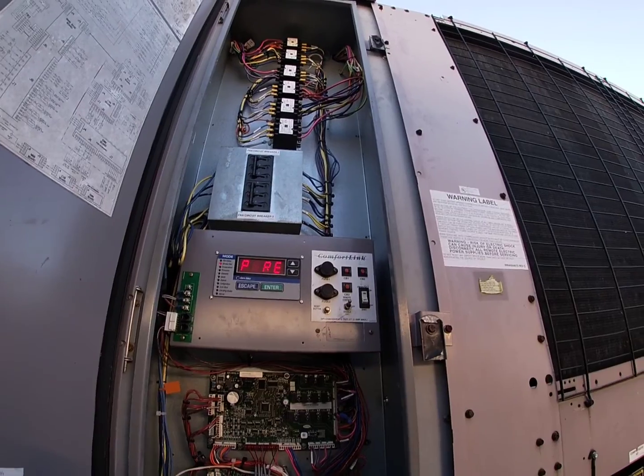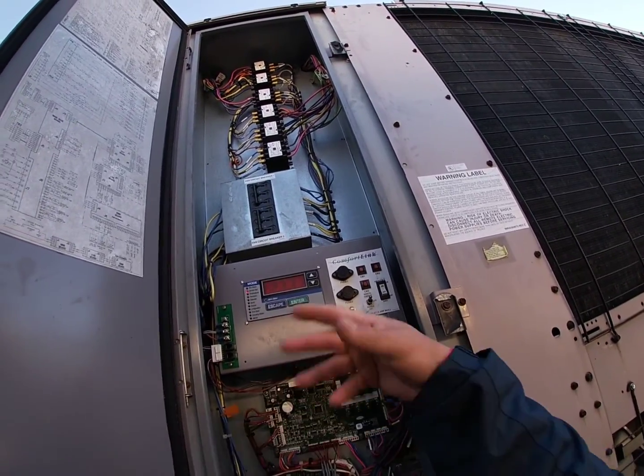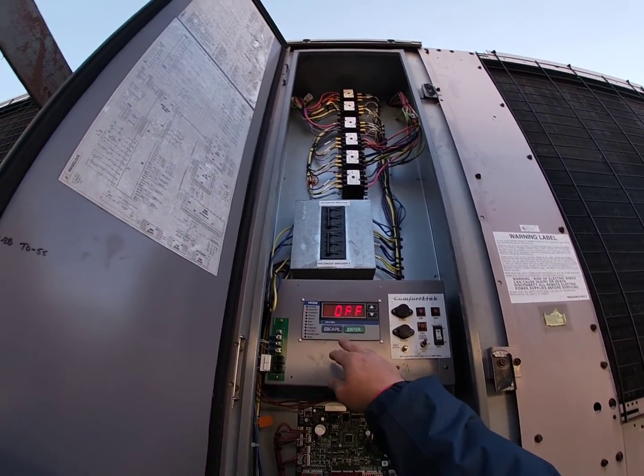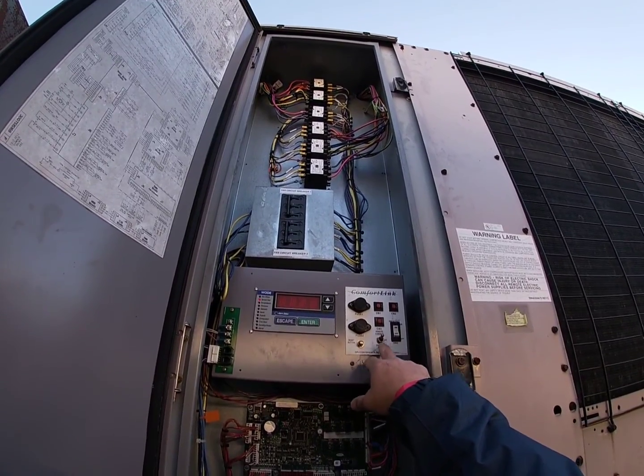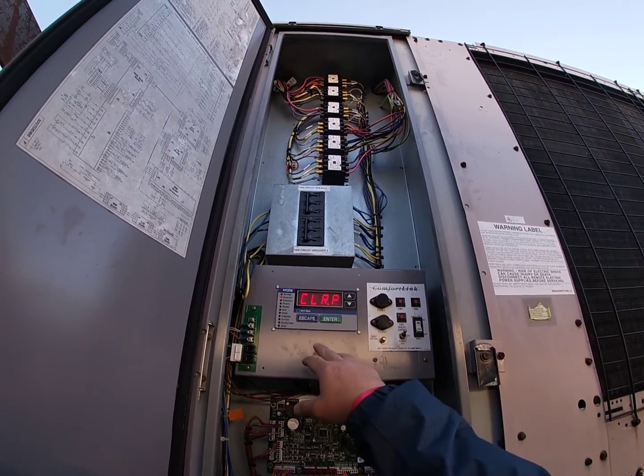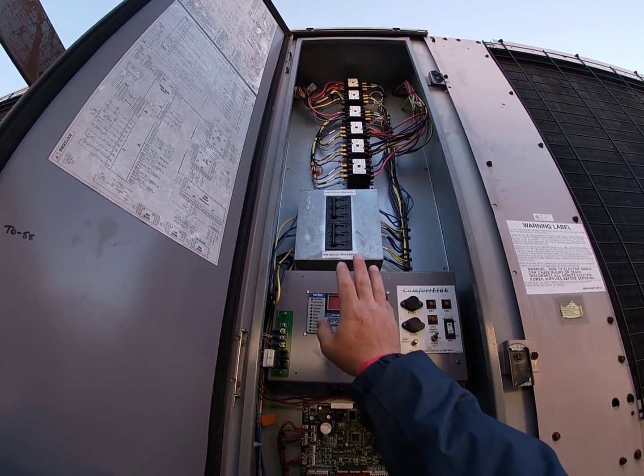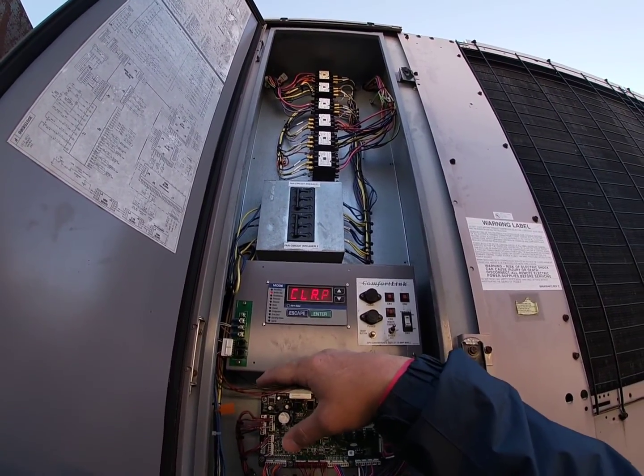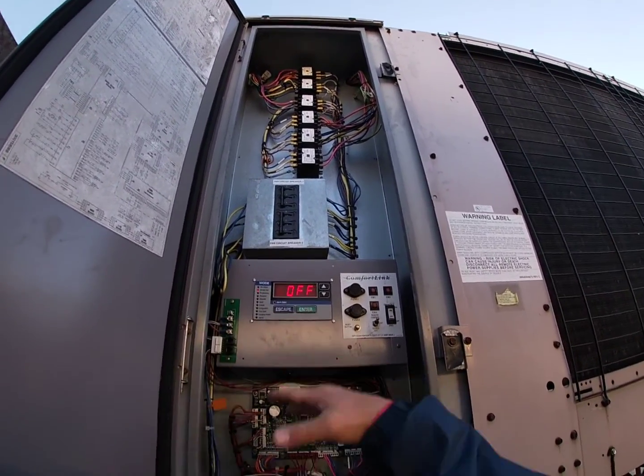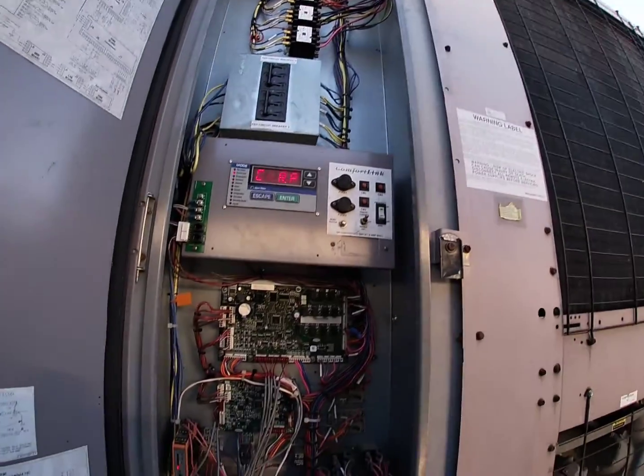Cooler pump. So earlier when I saw that alarm, that was the first thing I did. I reset the alarm. I went in here, put the switch in off or in remote, whatever, and went and put it in service test, and I forced the pump to come on. I heard the relay click.